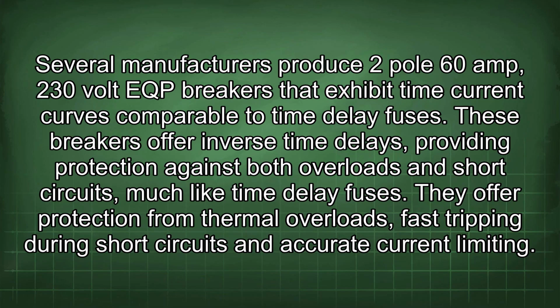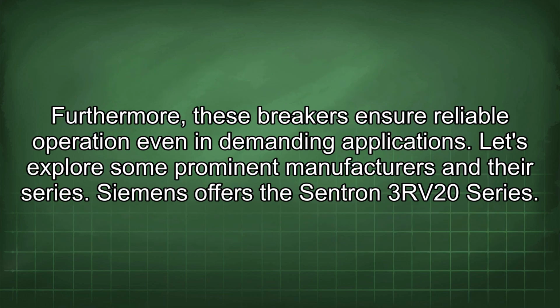Several manufacturers produce 2-pole 60-amp, 230-volt EQP breakers that exhibit time current curves comparable to time delay fuses. These breakers offer inverse time delays, providing protection against both overloads and short circuits, much like time delay fuses. They offer protection from thermal overloads, fast tripping during short circuits, and accurate current limiting. Furthermore, these breakers ensure reliable operation even in demanding applications.